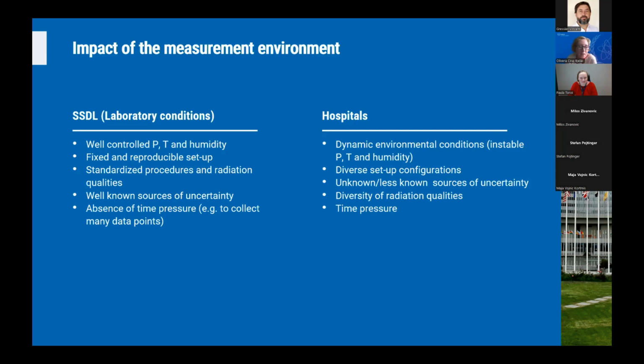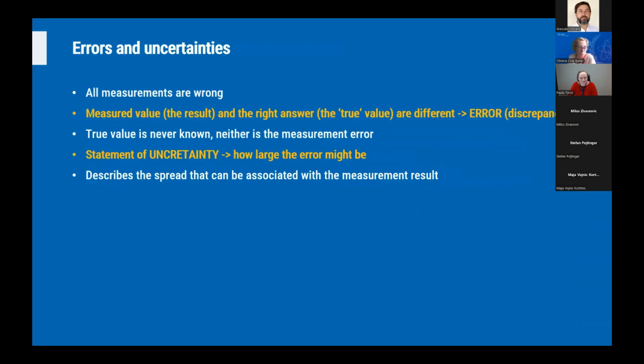As opposed to laboratories, hospitals are a dynamic environment with relatively unstable environmental conditions. It's sometimes enough that someone opened the window and we have a flash of hot air or humidity. Diverse setup configurations are used, very often not in a reproducible manner, which implies that sources of uncertainty are not well controlled and known. We have a diversity of radiation qualities. This was also discussed in the previous talks, especially by Stefan, and we normally have a time pressure of patients coming for examinations and very limited time to perform the measurements. And all these facts, in fact, have an impact on the accuracy of measurements in hospitals.